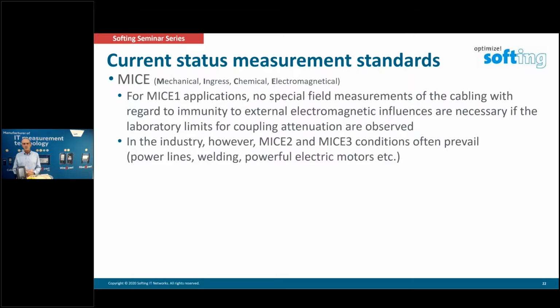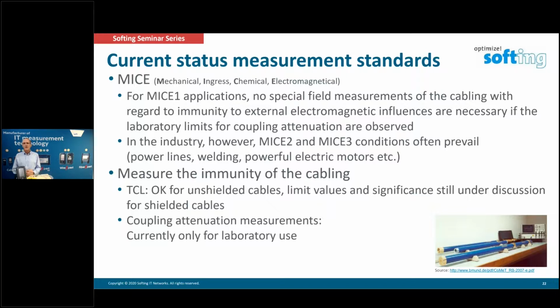In laboratories, that is feasible with coupling attenuation measurements. You're going to see that down here on the bottom. That is a measurement for coupling attenuation in the laboratory. So the blue tube here is basically a sensor. It's a current clamp, and you run a piece of cable inside that clamp. And on the bottom there, you have a spectrum analyzer worth 80,000–90,000 euros. So you can imagine that's not quite what you would like to have as a handheld tester.